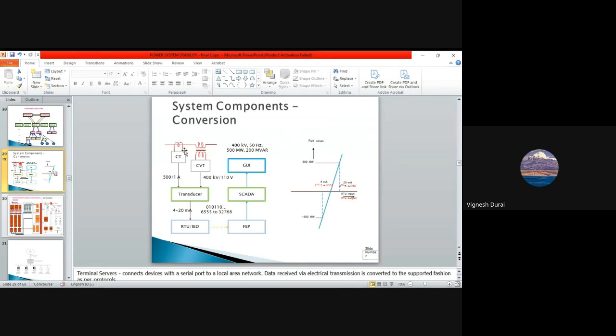See, this is a line where we will use a CT and CVT at the same time. You have a transducer. It will give input to this. Again, RTU, FEP front-end processors, SCADA, and graphical user interface. This is how the system components conversion happens.